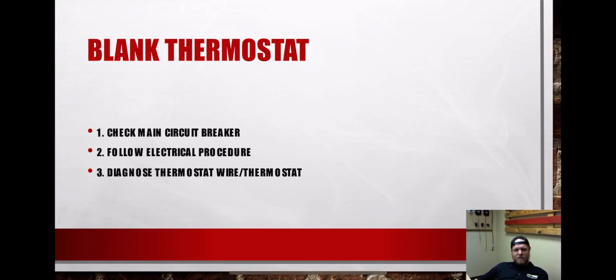You want to go up to the roof. You want to shut your disconnect down and run through your entire electrical procedure. Check everything, all your loads for shorts and grounds. Inspect all the wiring. Inspect your unit. Diagnose your thermostat wiring, your thermostat. Make sure everything is good as far as all that goes. Leave your disconnect shut down up on the roof.